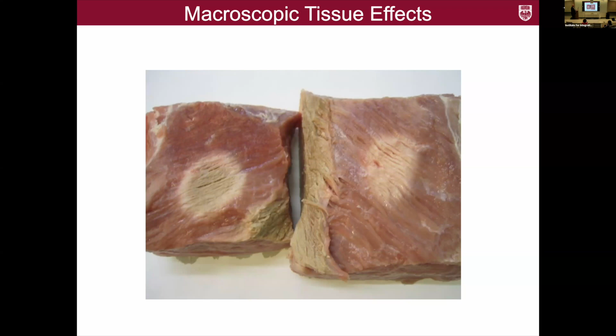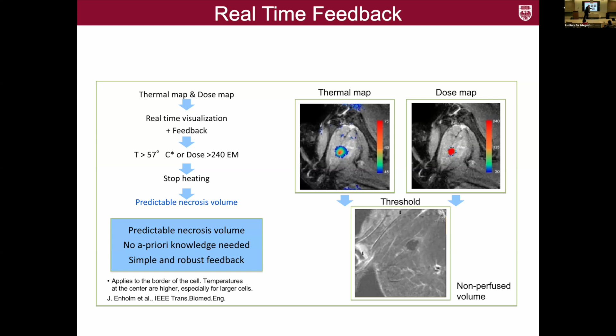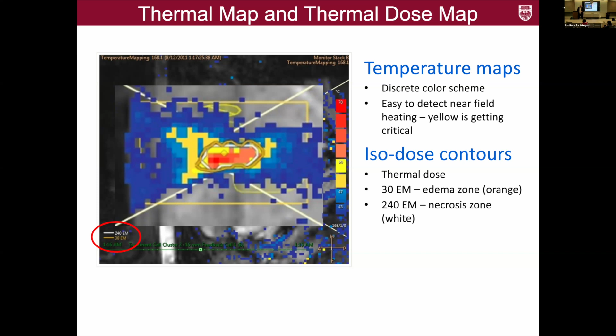We have real-time feedback in our MRI scanner, so we permanently calculate these thermal maps and the dose maps. Then we have the visualization on the screen. We can see what happens. And then once we heated up the tissue to 240 equivalent minutes, we stop the heating, and then we have a predictable necrosis volume. And you can nicely see after the treatment, in the MRI image, the treatment effect is also visible. Then we can see here again our temperature maps in color coding, and then we have the isodose contour lines like in radiation therapy. So we have here the orange for 30 equivalent minutes, and then the white one describes the necrosis in the tissue.